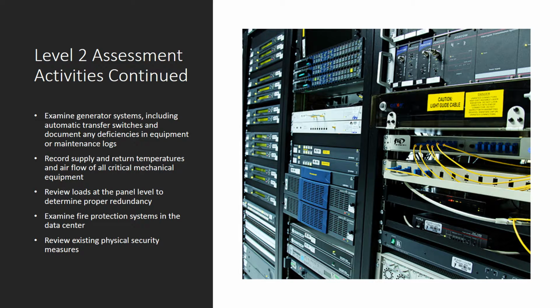All of the generator systems, including the automatic transfer switches, will be examined, and any deficiencies in the equipment or maintenance logs will be documented. All of the supply and return temperatures, along with the airflow of all critical mechanical equipment, will be recorded. The existing physical security measures of the data center will be reviewed, along with the fire protection systems being examined. Lastly, a review will be conducted of all loads at the panel level in order to determine proper redundancy.